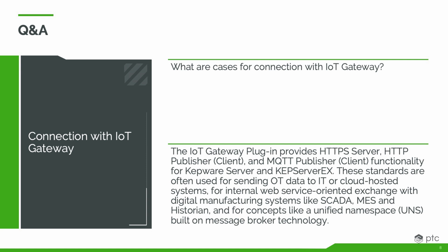We also have a server-side REST API, typically used in combination with the HTTP publisher. We'll publish information like set points, Boolean triggers, and control points to something like a manufacturing execution system, then use that passive server-side REST API to let the same system execute deterministic read and write operations for process control. In that sense, we've used IoT Gateway as a substitute for a superset API like OPC UA, simply because companies are more familiar with HTTP, or because they've built their own manufacturing execution systems using REST APIs, and Kepware just becomes another REST API. That's a perfect use case for IoT Gateway.